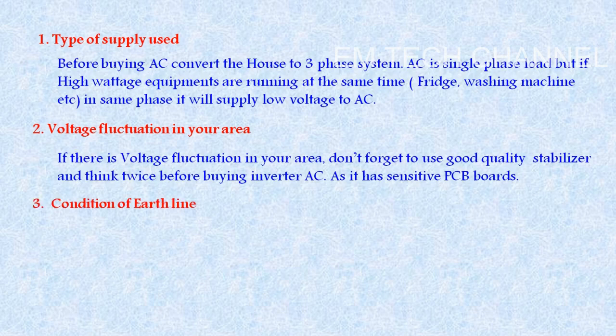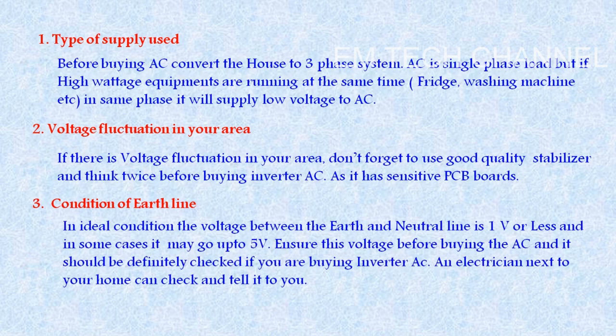Next, condition of the earth line. This is another important point. You have to check the earth voltage between earth and neutral, and the condition of the earth line installed in your premises. Ideally, the voltage between neutral and earth should be less than 1 volt, and in some cases it can go up to a maximum of 5 volts, not beyond that.